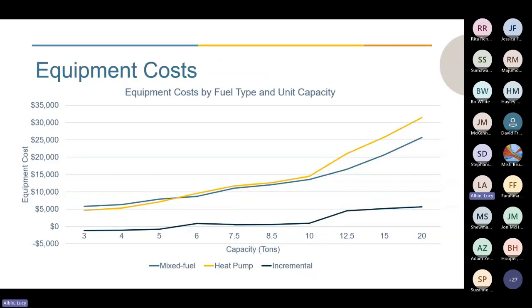So throughout this study, we also collected cost estimates for both the single zone AC and the single zone heat pump equipment from wholesale distributors and contractors. And we collected both material and labor costs, which are shown on this graph here, which has the comparative costs for different capacities, as well as the incremental cost, which is shown on the black line near the bottom. And as we can see here, this shows that heat pumps are actually less expensive than their mixed fuel equivalent for smaller sized units in the 3 to 5 ton range. At that point, the mixed fuel equipment becomes greater, but the 2 costs stay relatively similar and relatively close up until 10 tons, where you can see that incremental cost jump up and see that gap widen with the heat pumps becoming more expensive.